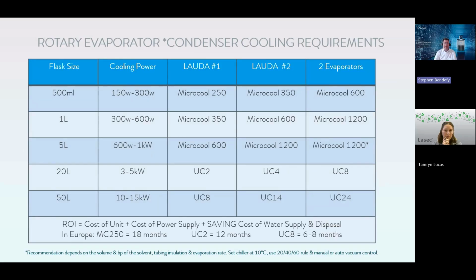So then we very often get the question, what is the payback and what can we use? We have a variety of different machines available, going from small 250 watt cooling machines that could be suitable for 1 or 2 rotary evaporators, for example, or you may choose one machine to connect to 4, 6, or 8 systems, so that there's one chiller providing the cooling for multiple units.